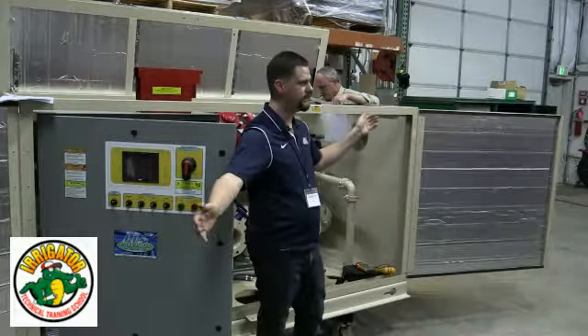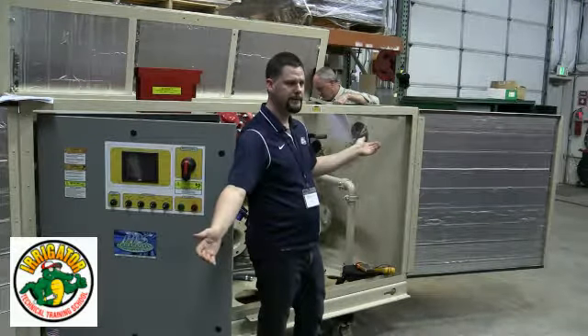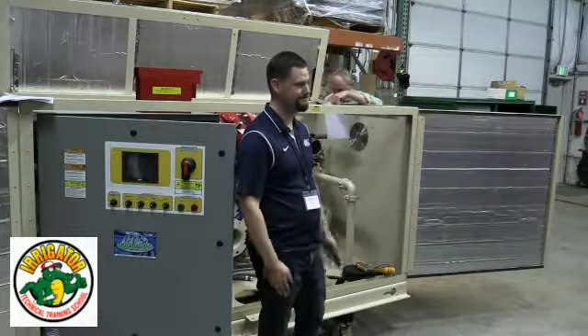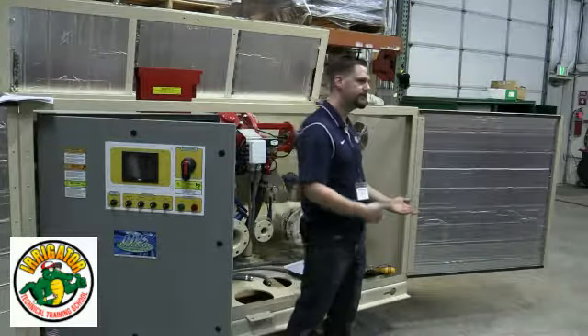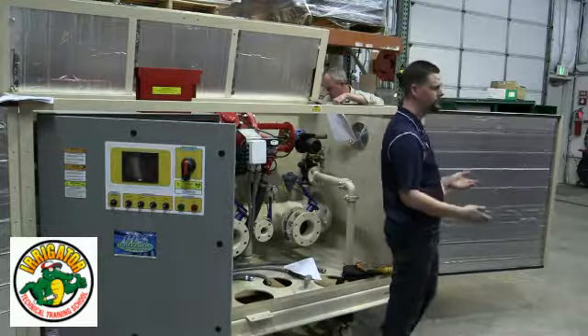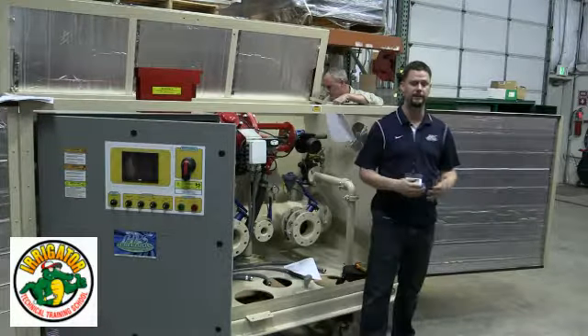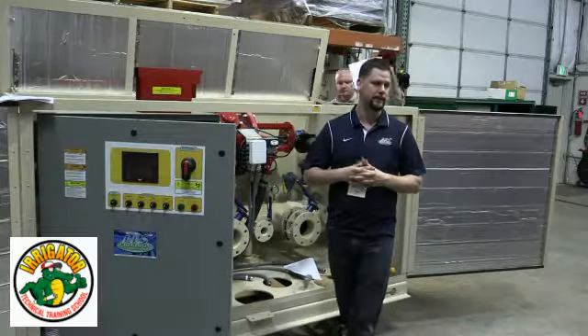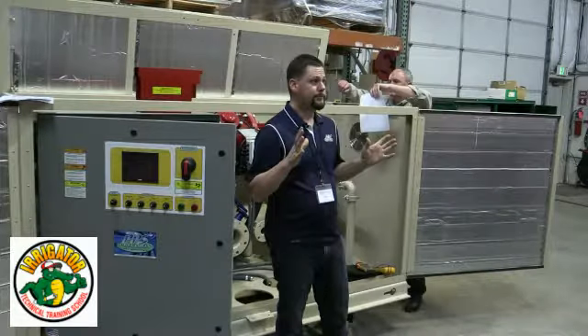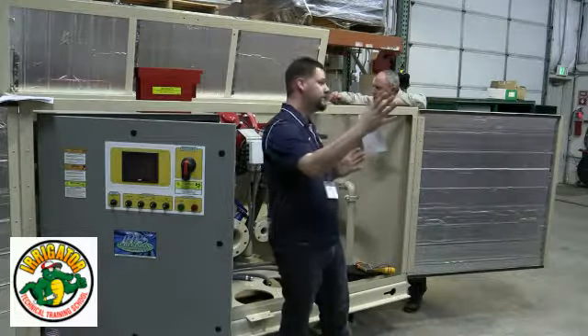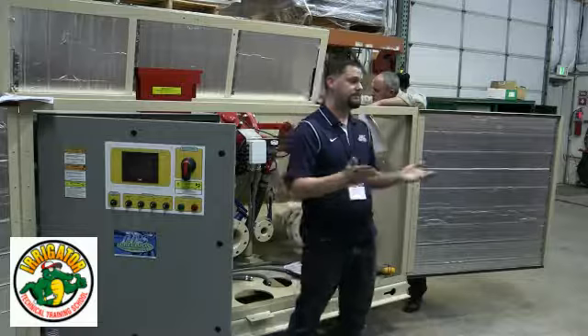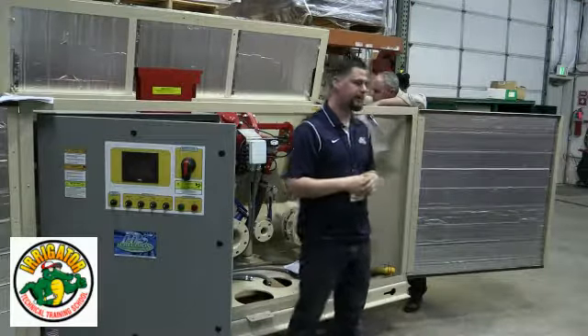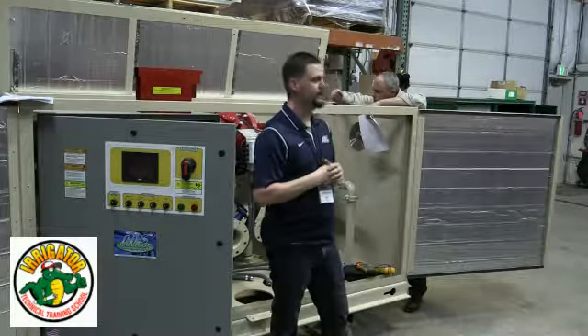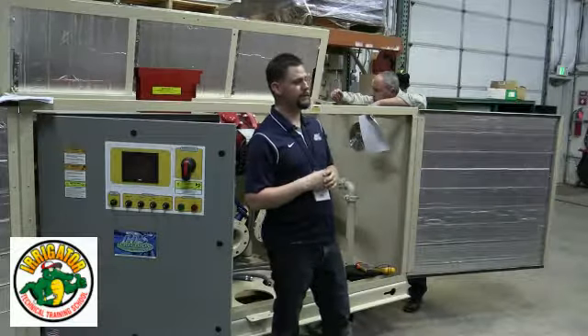Because if we're a couple feet short, it's still going to work, just not as accurate. So instead of being plus or minus 2 or 3%, we're going to be plus or minus 10 or 15%, depending on the turbulence in the water. So if accuracy isn't that important to you, the DEQ isn't breathing down your neck, you just want a general idea, that may work—it may work real good. But in this case the guy said, we just got a bunch of money, so quote us a mag meter.